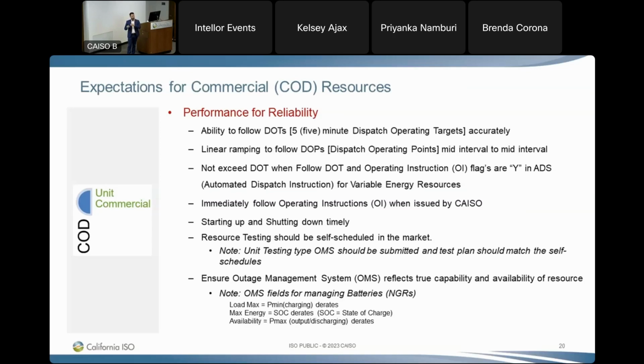When we have congestion on the system, you are now a COD resource, you are now participating in the market. If there is congestion on an element, you may receive an ADS operating instruction flag of yes, follow DOT, if your resource is contributing to that congestion. It may be telling your resource to increase, or it may be telling your resource to decrease. When you're receiving that flag, regardless if you're a VER or a solar site, you need to be following that instruction. If you're not following that instruction, you're basically not following your tariff obligations. You need to follow those dispatches when we are giving you instructions to follow your DOTs at all times.